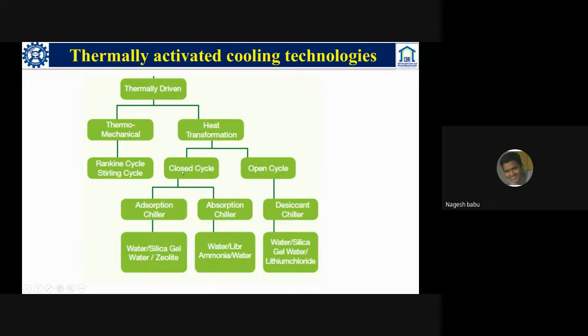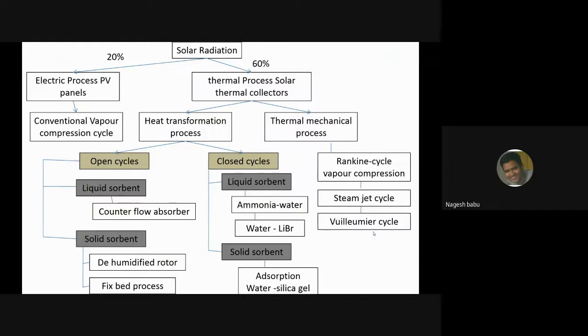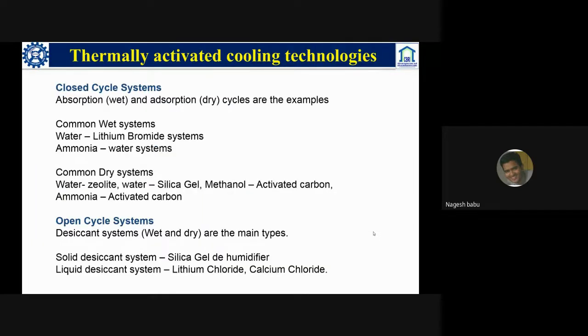Again, it is classified as closed cycle and open cycle. Under closed cycle, we have adsorption and absorption chillers, and under open cycle we have desiccant chillers. We have different types of refrigerants for adsorption as well as absorption, and we are going to briefly discuss the desiccant chiller, that is water silica gel, on which we are actually working. I have briefly discussed various types of technologies as well as various types of solutions. Similarly, for closed cycle, we have absorption and adsorption.